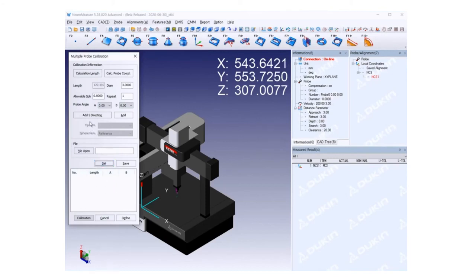But I'm going to click add 5 directions, which is very commonly used, the 5 different angles. The first one is 0, 0, and then all the other 4 different directions. And then I'm going to add A 45 degrees and B 67.5 degrees, added as a 6th position of probe angle. And after all this list is made, click calibration, and then it'll automatically start multi-probe calibration.